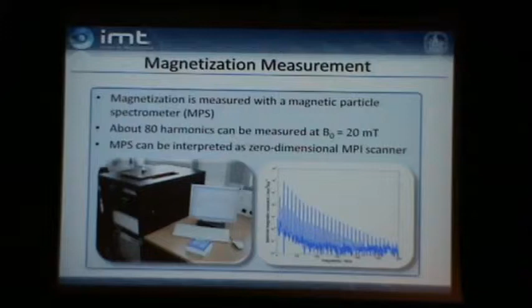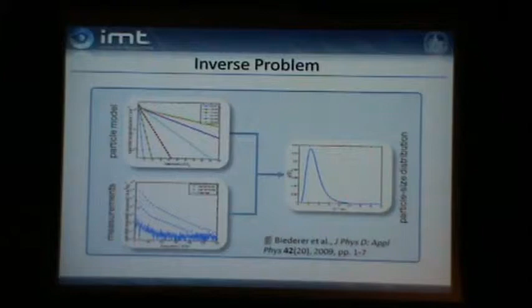fundamental frequency. Okay, this is the signal that we have measured. We have seen 80 harmonics when we excite with 25 kilohertz. And what we also did, based on the Langevin theory, is solve the inverse problem. When we have the theory and we have the measurement, then we can fit the parameters and receive a distribution of particle sizes. So our spectrometers then give as an output this distribution of the particle core sizes.